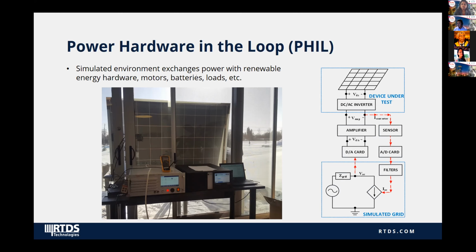Or if you want to provide instrument-level voltages and current, you can use an amplifier to amplify them into instrument levels, like 110 volt or 5 ampere, and then feed that to your protective relay. For this type of testing, you need the simulator plus an analog output card to provide voltage and current signals, and a digital input card to get the trip signal back to the simulator so you can control your circuit breaker. If you want to provide circuit breaker status back to the relay, you might need another digital output card. And if your protective relay model supports the IEC 61850 approach, you don't need an analog or digital output card. Instead, you can use a network interface card with industry standard protocol. For relay testing, we basically use IEC 61850 sample values and GOOSE.